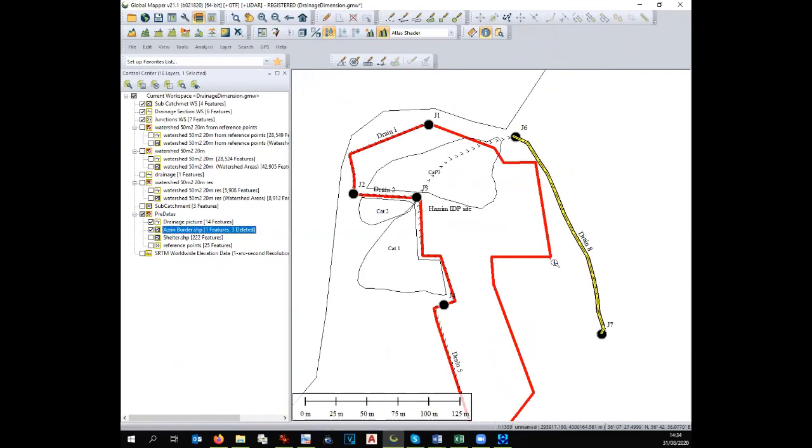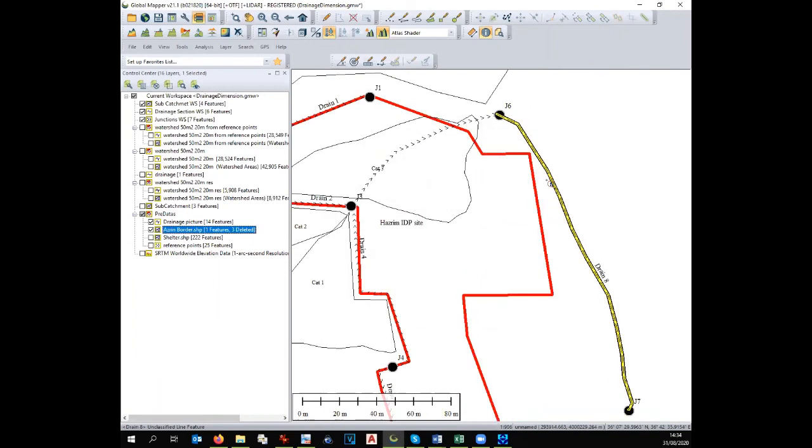One mitigation measure would be to make a drainage here, even if it's outside of the area. Maybe you are not allowed because it's another land and the owner doesn't allow you to put any drainage. So what you probably have to do is increase the elevation of this area here, with more gravel, or make a protection of this area against flooding.